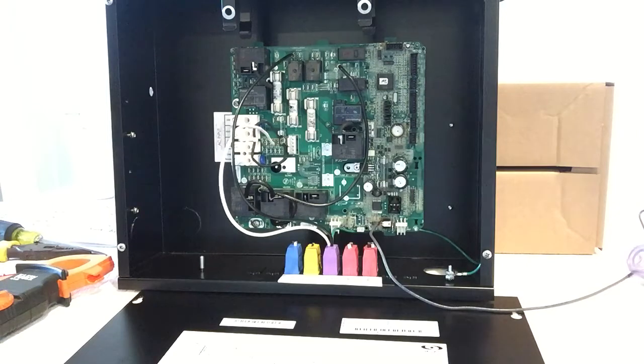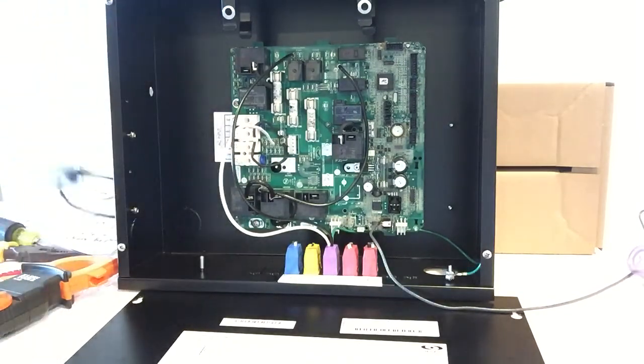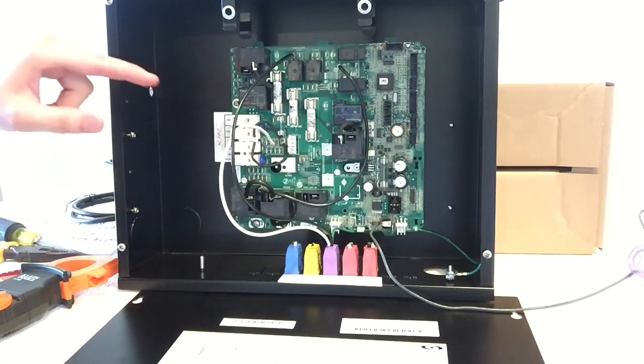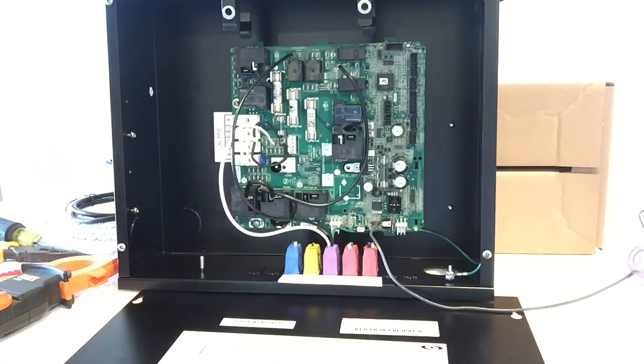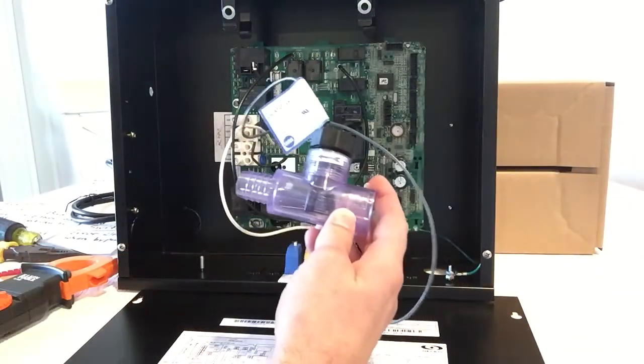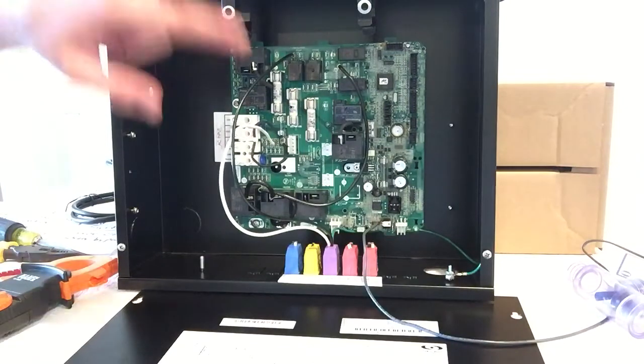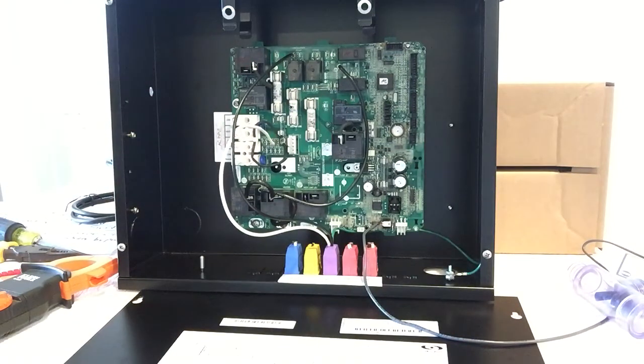So when it comes to a flow error, it can be a few things. It can be the circulation pump is not running properly or not running at all. It could be that the fuse is blown on the PC board for your circulation pump. It could be that your flow switch is not working properly. It also could just be your PC board, this whole green thing in here, is bad. So here are a few tests to try to figure out which one of these it is. Majority of the times, it's a flow switch or the circulation pump. Sometimes it's the fuse, rarely it's the board, but it does happen.